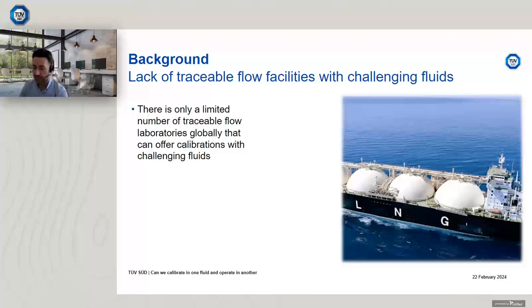However, we're currently in the situation just now where not enough research has been completed, or there's simply a lack of facilities to even validate as to whether a water calibration will transfer to CO2 or hydrogen, and LNG as well. It's almost like a chicken and egg situation we're in just now. We know what we want, and we're hoping a water calibration or an air/nitrogen calibration might transfer, but simply there's not enough data at present to say with any conviction whether it's the case or not. Ultimately, you want to see the data.